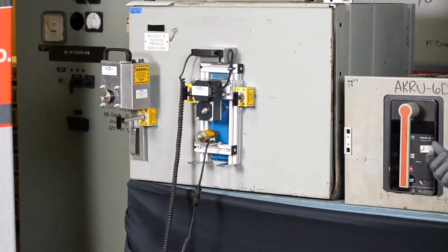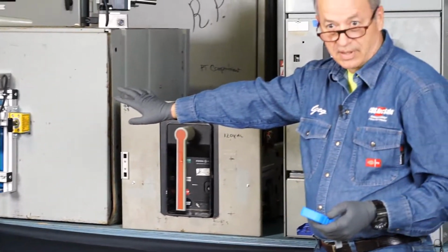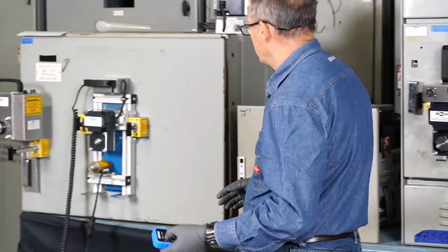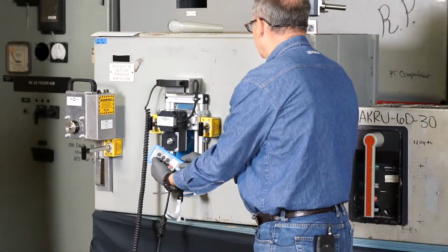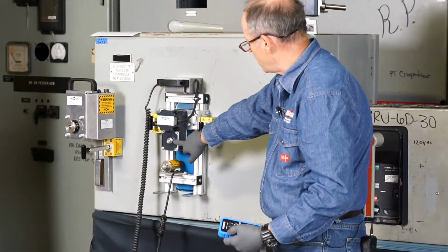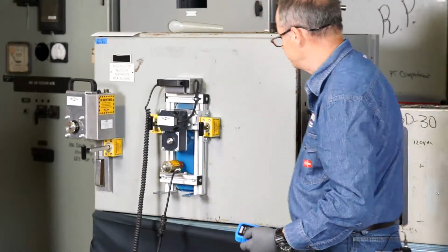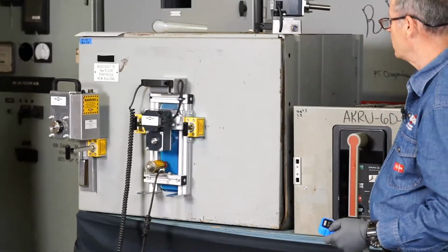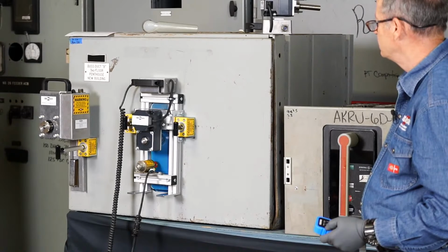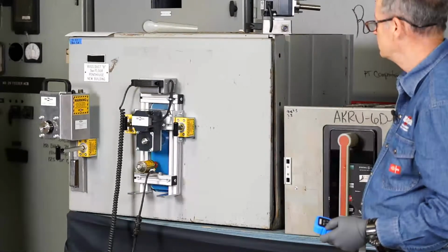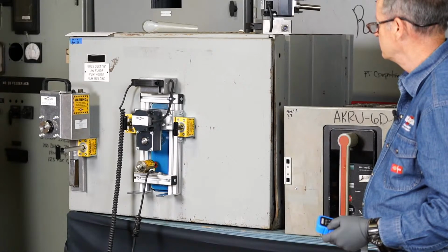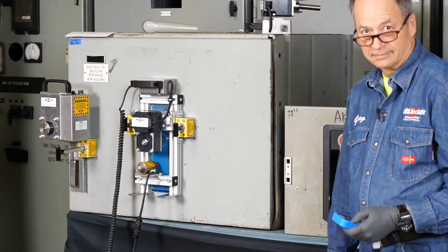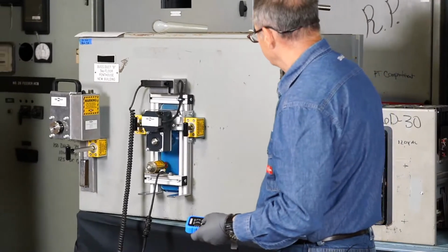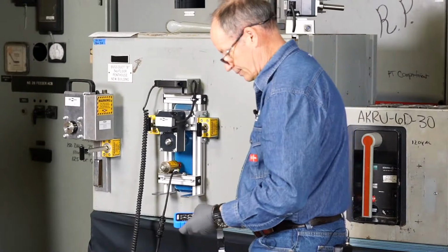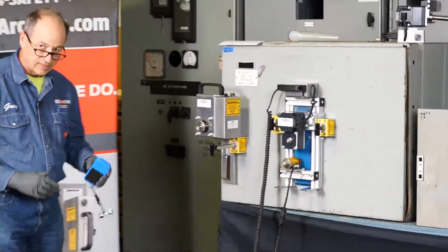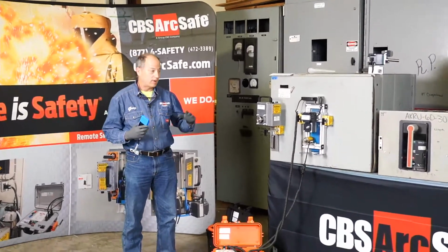If we were going to just trip the breaker, then we would take this off. We would go to the racking part of the operation. If we want to see ourselves do the charge close now, we can actually punch the charge close on here. The system's going to start going through the process of charging and closing this circuit breaker. And it's actually going to trip free just because of this breaker. So be ready for a loud boom when it does this. So that's basically how this system would operate to allow us to close or trip the breaker.